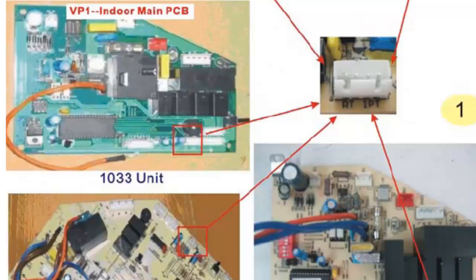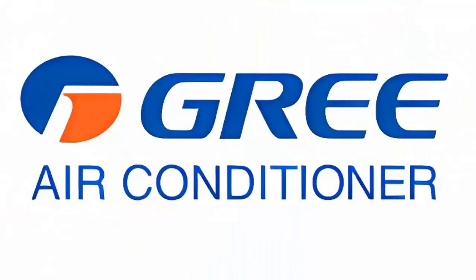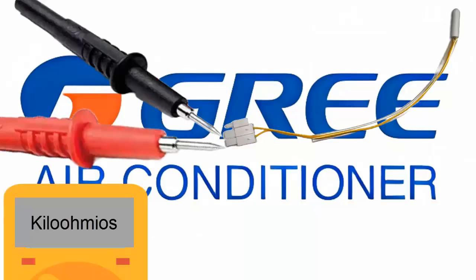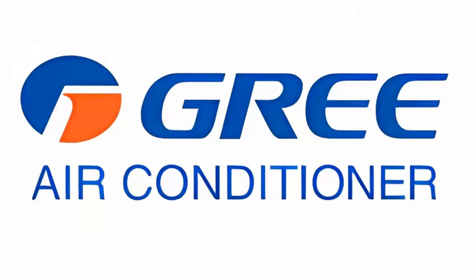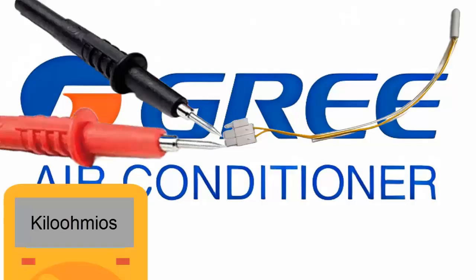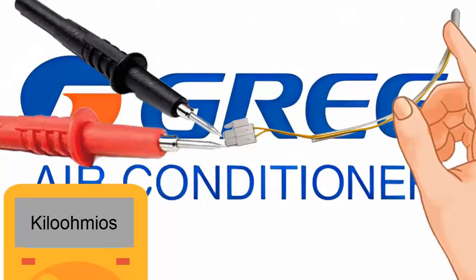6. If the error persists, turn off the unit, disconnect the sensor, and measure its electrical resistance with a multimeter on the kilo-ohm scale. The measured value should never be 0 or infinite. Otherwise, replace the sensor. Remember that when you rub the sensor with your hand, the resistance value should decrease. Otherwise, replace the sensor.